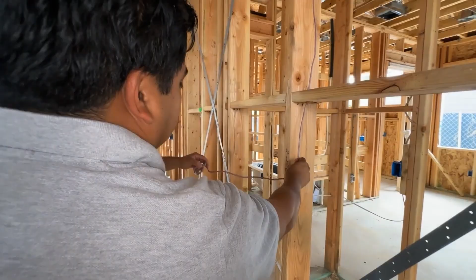We like to place these thermostats as close as possible to the return, because that's what sucks in all the hot air. You don't have any supply vents coming into the hallway, that's the purpose. You want the thermostat as close as possible to the return and as far as possible from a supply vent. If you have a supply vent or cold air vent near the thermostat, it's going to shut the system off before the whole house is fully cooled down, because you'll have a really bad sample of the house.